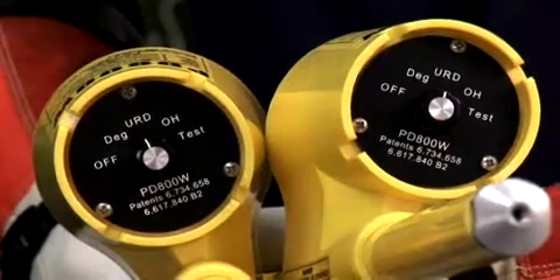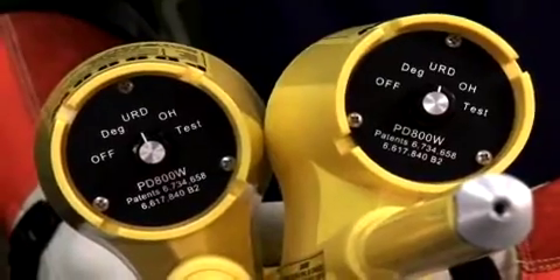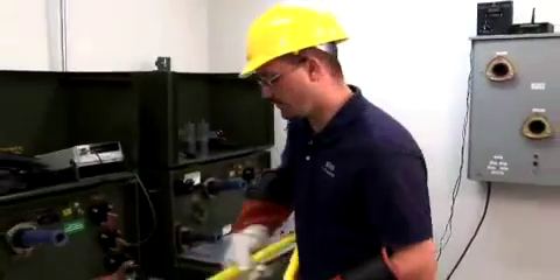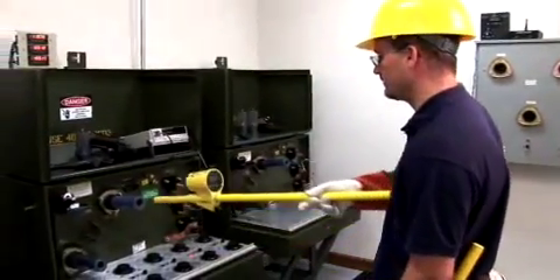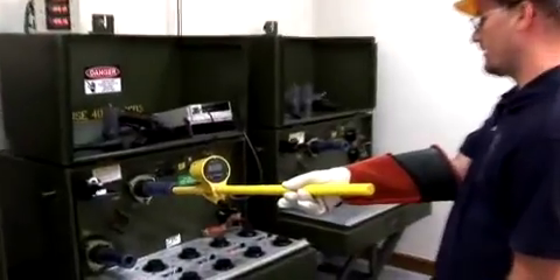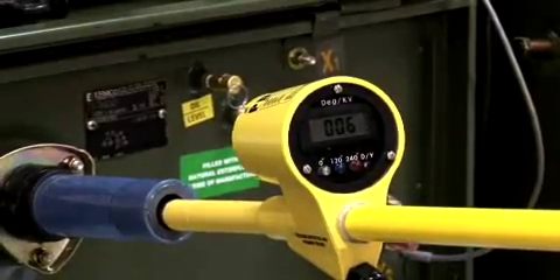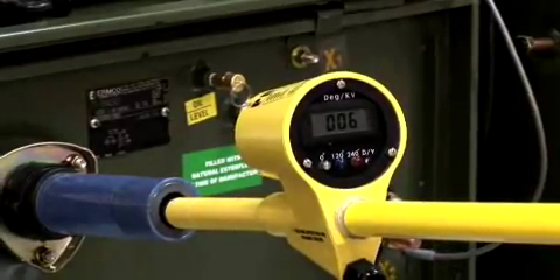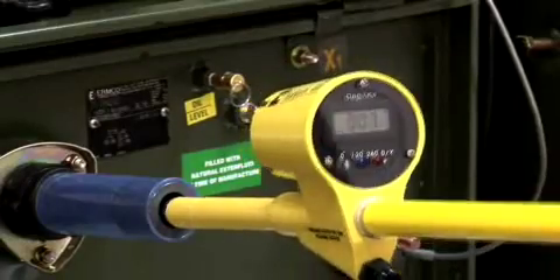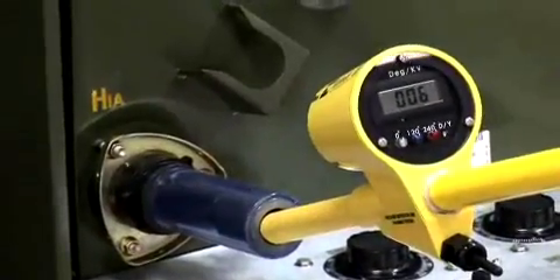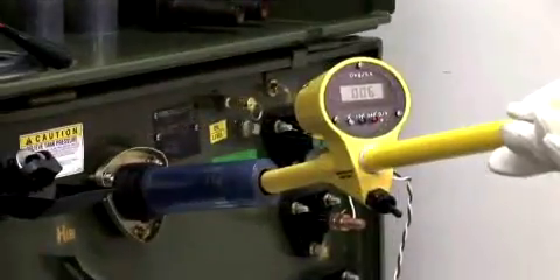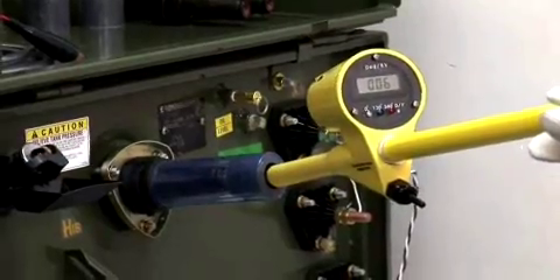We're measuring underground, so we have both positions in the URD position. Okay, so we're going to use the meter probe as a voltage detector. Make direct contact. Okay, on our 7200 volt line, we're measuring about 6 kV on this bushing. Same on the bottom bushing. The same on the other transformer.